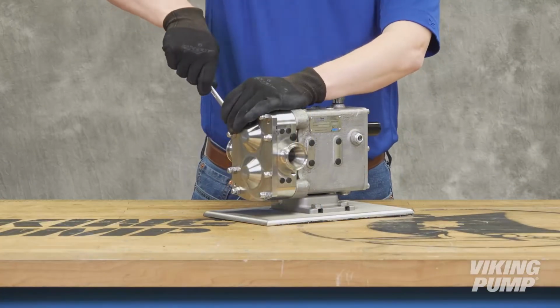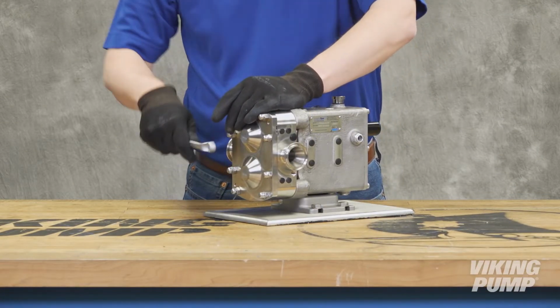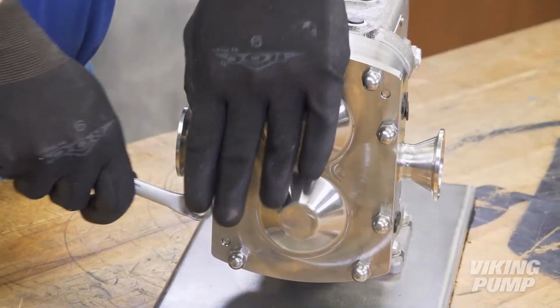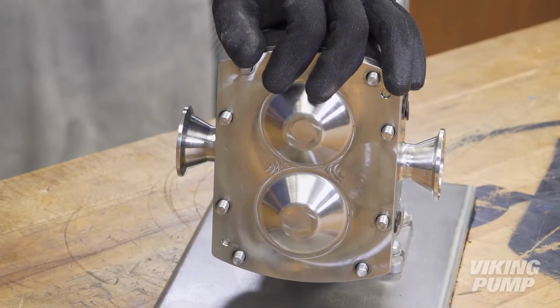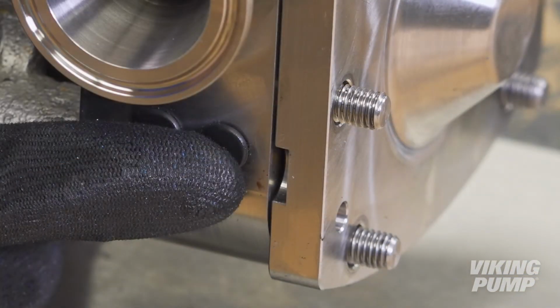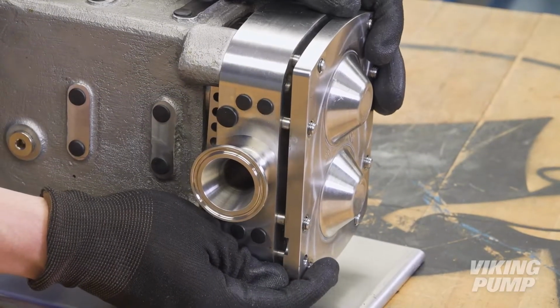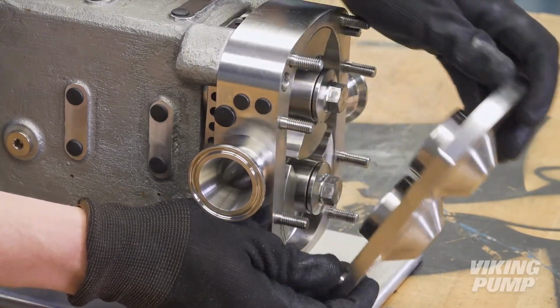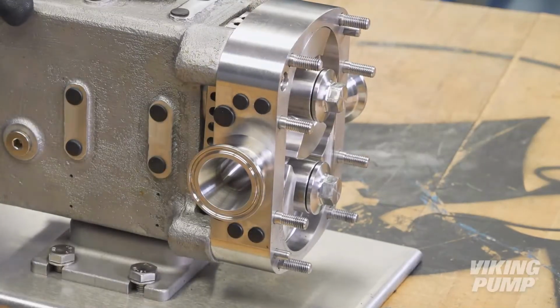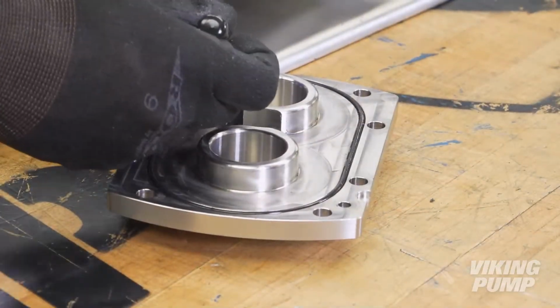To begin, loosen and remove the pump cover dome nuts and remove the pump cover. Ears or cutouts located on the front cover can aid with removal. If needed, use a soft-headed hammer or flat screwdriver to slide the front cover off the locating dowels. Remove the pump cover O-ring.